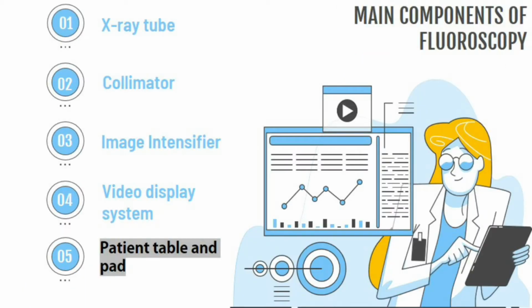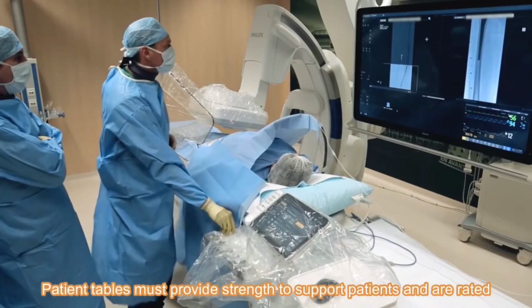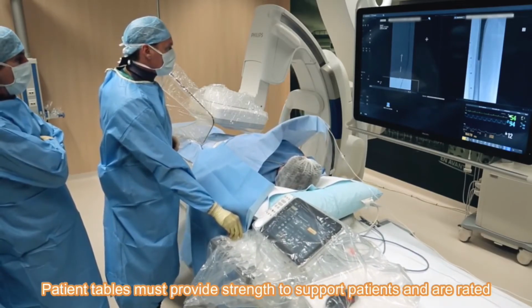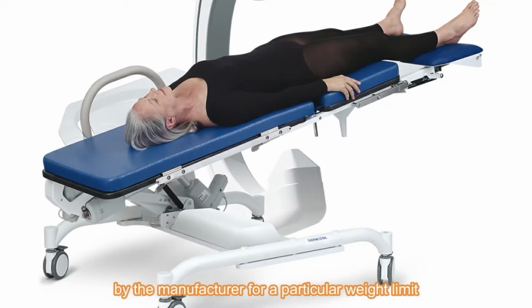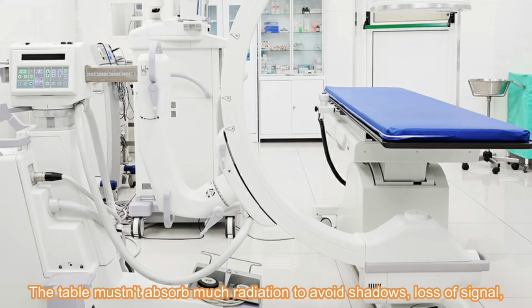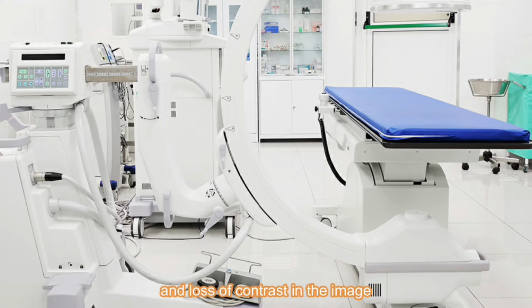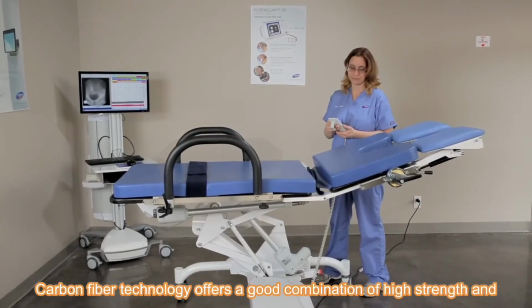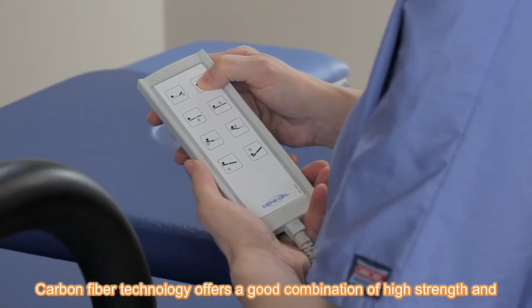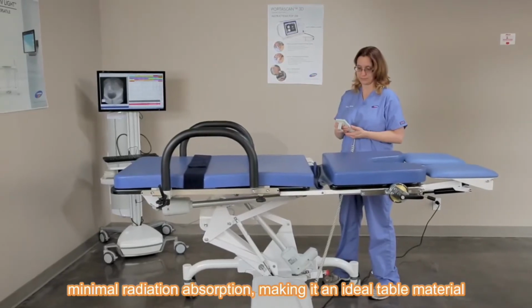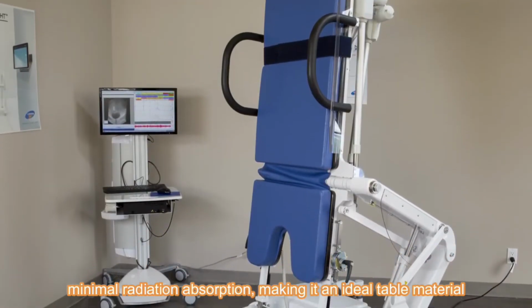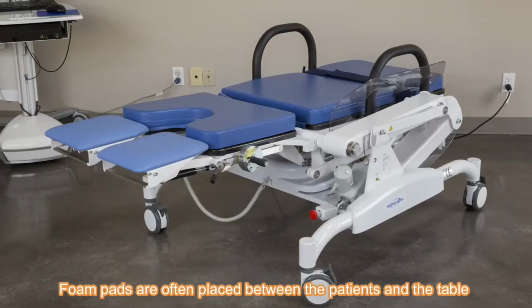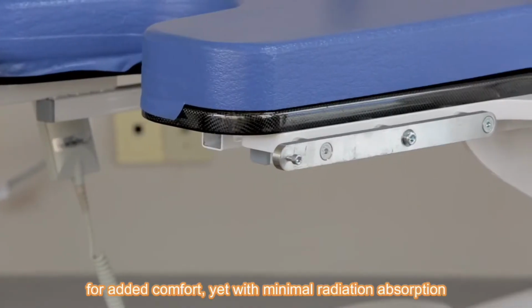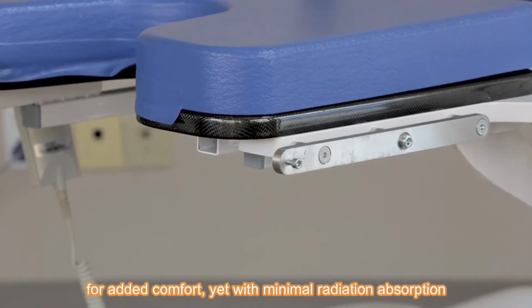The last one is patient table and pad. Patient tables must provide strength to support patients and are rated by the manufacturer for a particular weight limit. The table must not absorb much radiation to avoid shadows, loss of signal, and loss of contrast in the image. Carbon fiber technology offers a good combination of high strength and minimal radiation absorption, making it an ideal table material. Foam pads are often placed between the patients and the table for added comfort, yet with minimal radiation absorption.